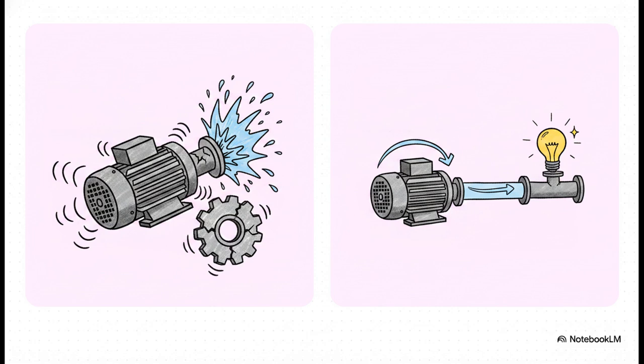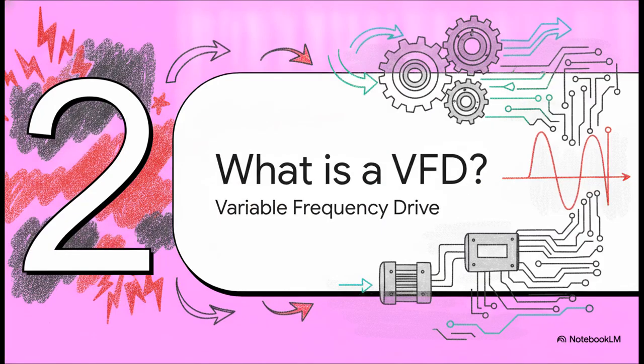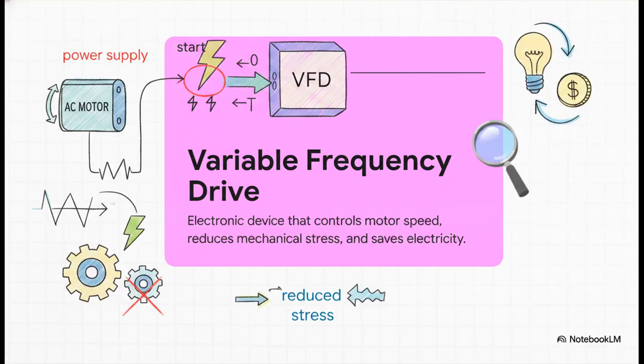But switch over to VFD control, and suddenly you get this beautifully soft, precise start, giving you massive energy savings and far less wear and tear on the mechanics. Which brings us perfectly to Section 2. What is a VFD? So what actually is it? Basically, a variable frequency drive, or VFD, is a vital electronic buffer in industrial automation. It sits right between the main power supply and an AC motor. Its whole job is to dictate exactly how much energy that motor receives. By doing that, it reduces mechanical stress, gets rid of that violent starting current we just talked about, and dramatically cuts down on wasted electricity.